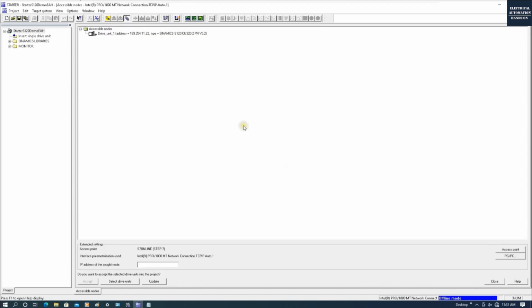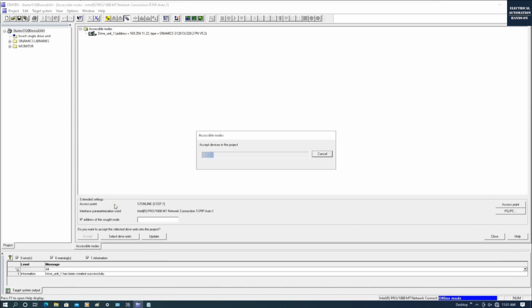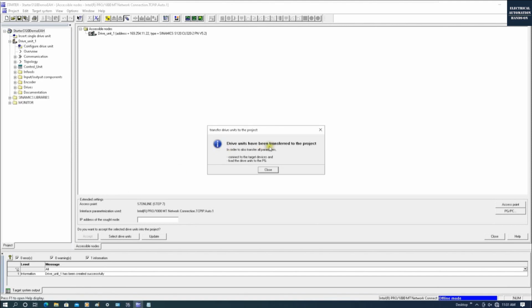When we do the commissioning, basically we are connecting point to point, just commissioning one by one. After we select this hardware, we click accept. Then the Starter software will try to connect to this hardware. The drive has been transferred to the project, and now this project can connect to the hardware. Okay, we can click this online.